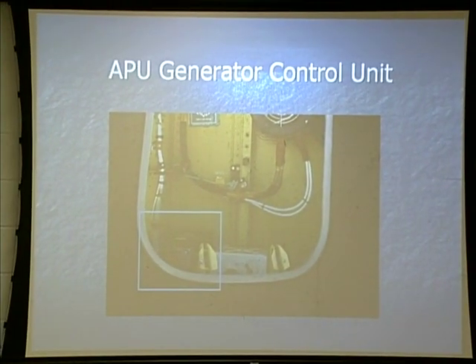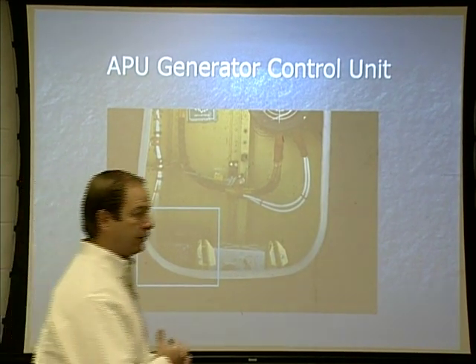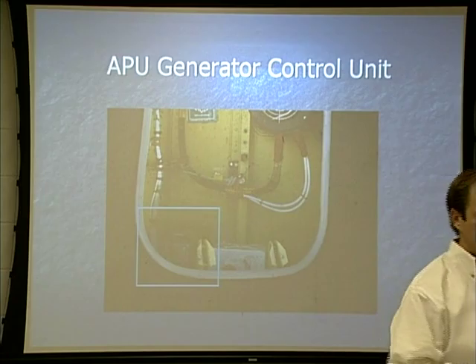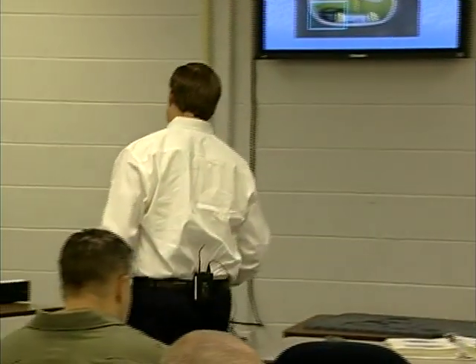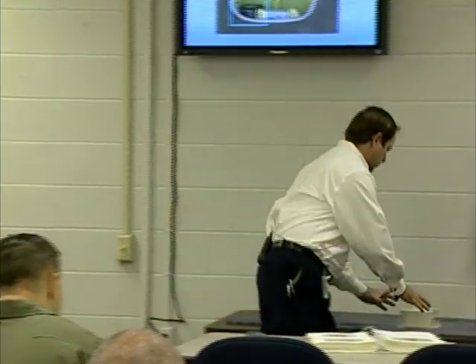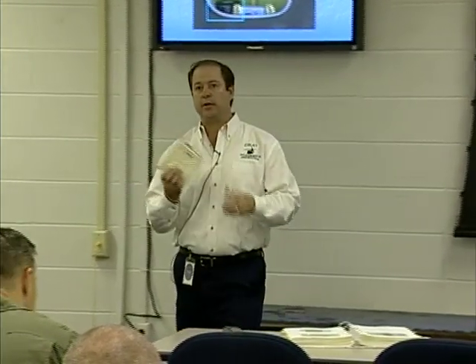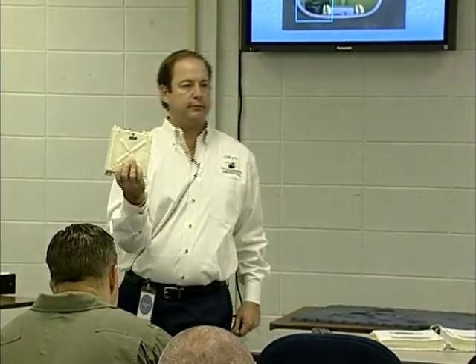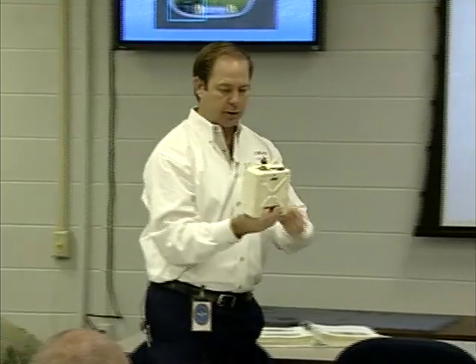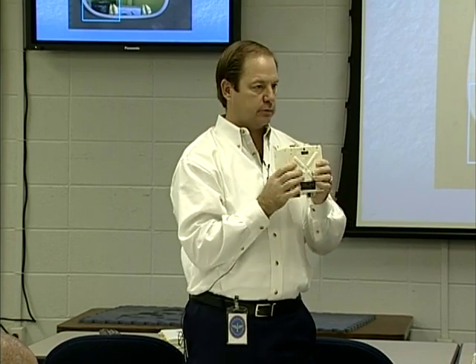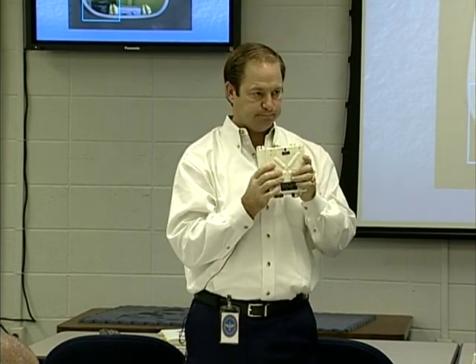Now I'm going to come to this picture, but we're not done with the main generator GCUs yet. Why? Two things. One, the main generator GCU has what's called a BITE indicator, built-in test equipment. It consists of one of those magnetic latch indicators. It's going to trip black and white if it senses a fault inside.